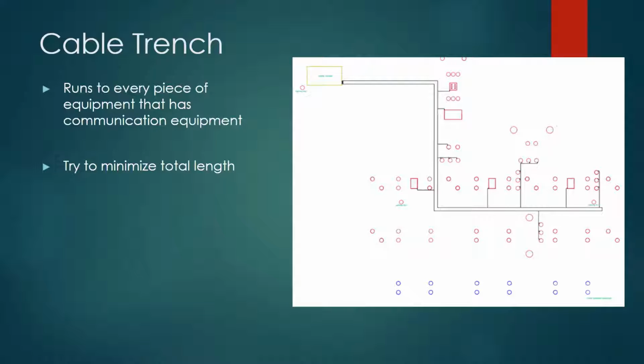We are trying to minimize the total length of our cable trench. We do that by running it out of the control house, down the side of the transformer and into the middle of the ring bus. This minimizes the total length of our trench while maximizing how much equipment we can get to.